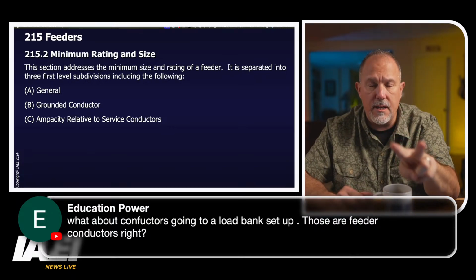You have two things to think about when you're dealing with conductors. The first thought process is the ampacity, the capability of the conductor itself. How much current can a conductor carry under a specified condition of use? And in 310.16, there's a table that gives you the conditions of use at the top. That's 3 current carrying conductors, whatever.